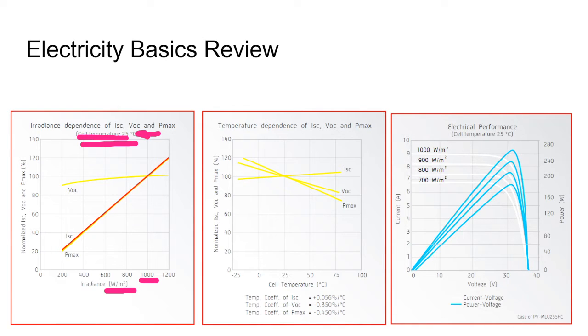And so this is actually more reflective of a colder day than 25C, because it's specifically done when the cell temperature itself is at 25C. And that's 77 degrees Fahrenheit. So this might be more like a 60 degree Fahrenheit day, not a 77 degree Fahrenheit day out in the field, because the cell and rooftop temperatures are higher than that. Again, you can get rooftop temperature off of PV watts if you want to start identifying what a standard test condition day is in your area.